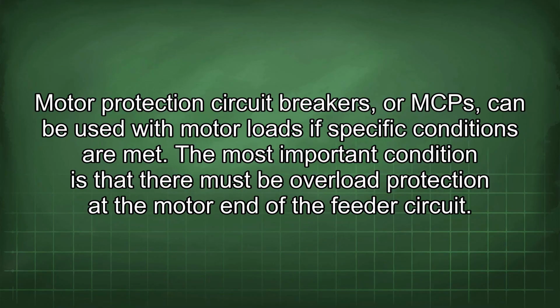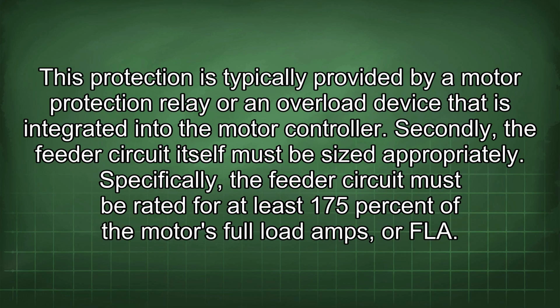Motor protection circuit breakers, or MCPs, can be used with motor loads if specific conditions are met. The most important condition is that there must be overload protection at the motor end of the feeder circuit. This protection is typically provided by a motor protection relay or an overload device that is integrated into the motor controller. Secondly, the feeder circuit itself must be sized appropriately.